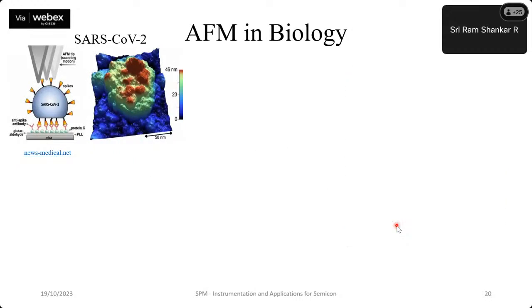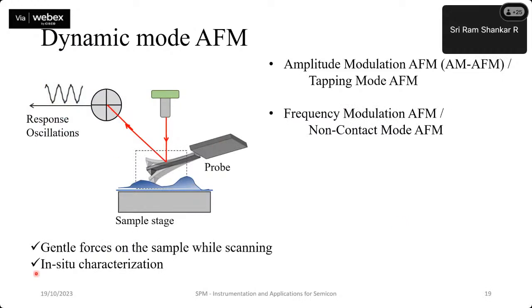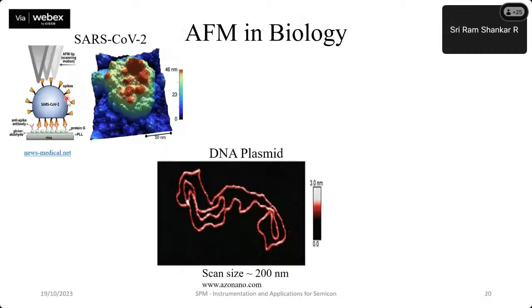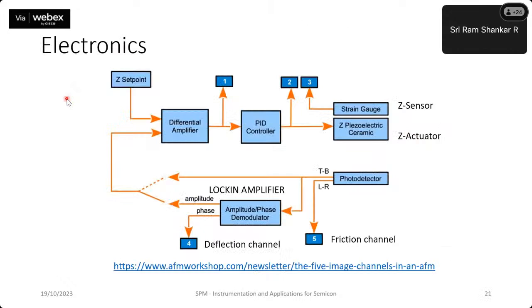We had a look at dynamic mode AFM, where we are vibrating the cantilever. Accordingly, the deflections we measure from the position sensitive photodetector will also be some sort of oscillatory wave, a sine wave. By looking at the amplitude and phase of these oscillations, we can perform a topography image and a material contrast sensitive image simultaneously. To perform such imaging, this is the sort of electronics you would need.